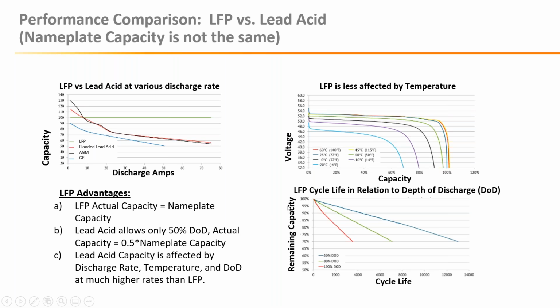And then I mentioned the cycle life in relation to the depth of discharge. So we are this green line here in the middle. At an 80% depth of discharge, we can usually guarantee around 6,000 cycles. And the same thing, if you want to do 50%, you could get more, and then at 100%, you could get less. You can go into like a 90% DOD if you want somewhere in the middle.